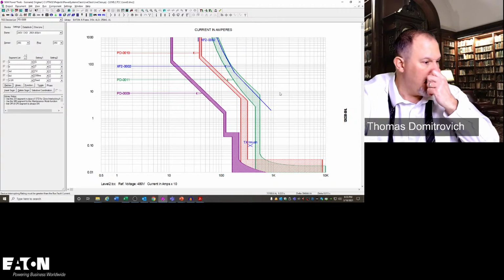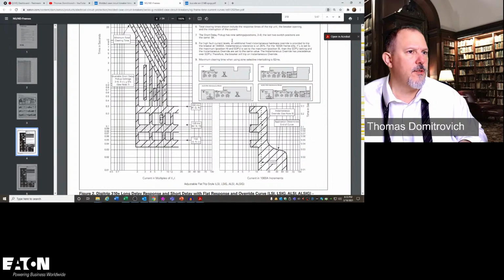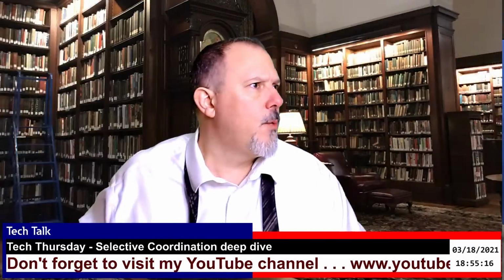And there was another question that I got on YouTube. I'm just going to go to Studio here and go to comments. And I have to unselect that. So the last question I got was regarding the cable selection: you selected the cable according to cable ampacity and you didn't check the cable short circuit capability. So how do we check to make sure that we're protecting the conductor when we're selectively coordinating? Because this is all a part of it.